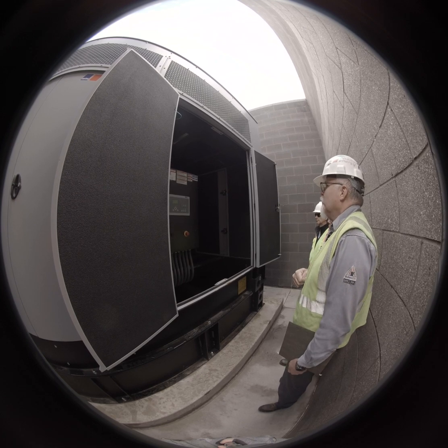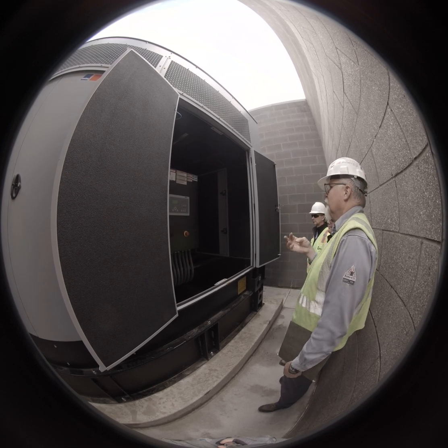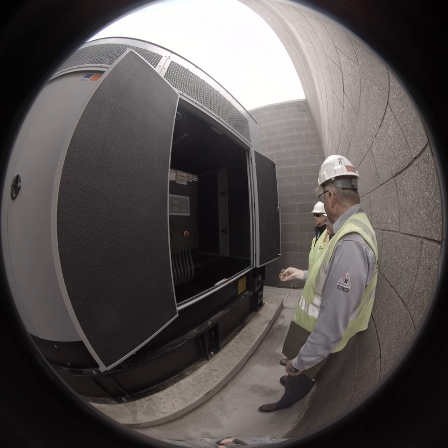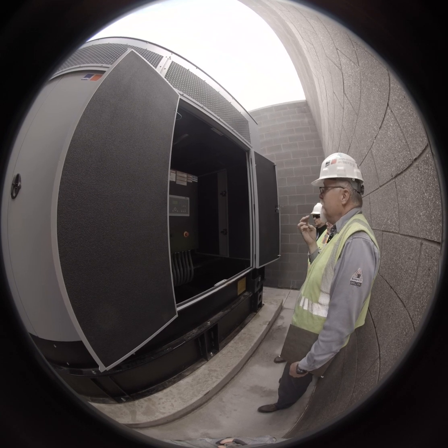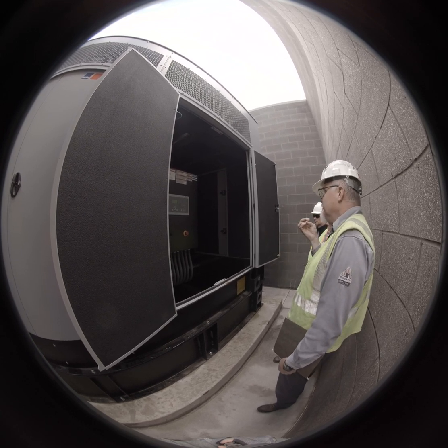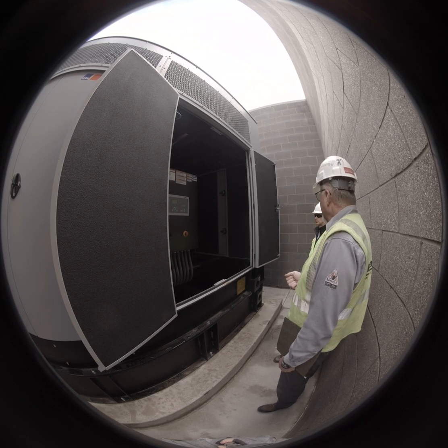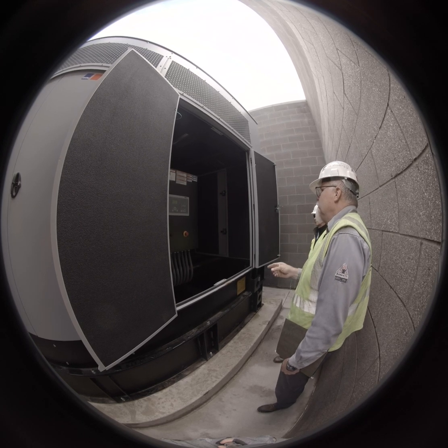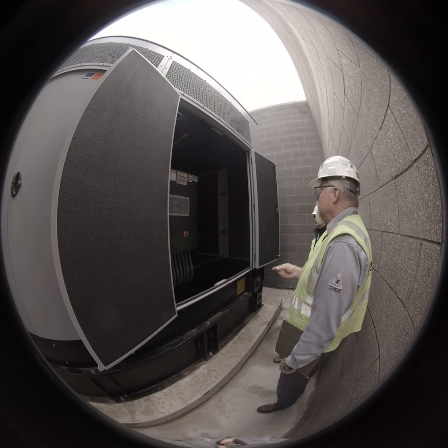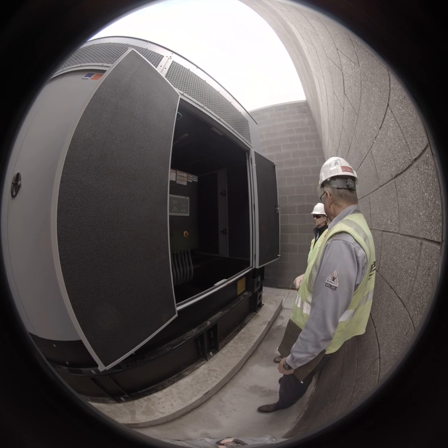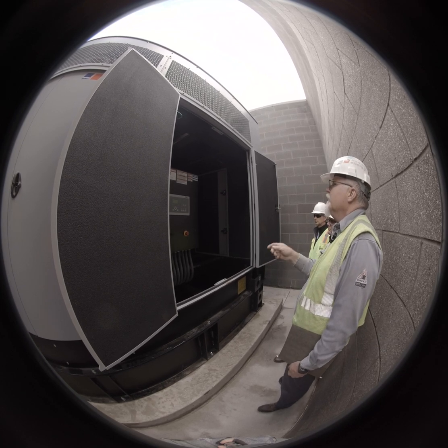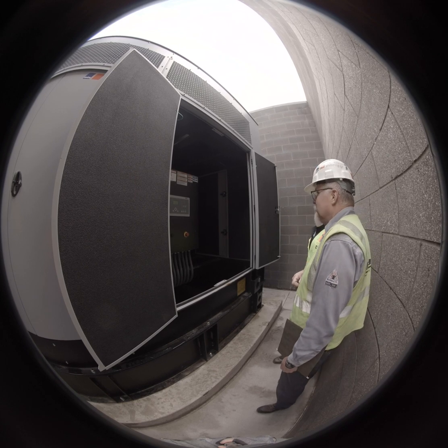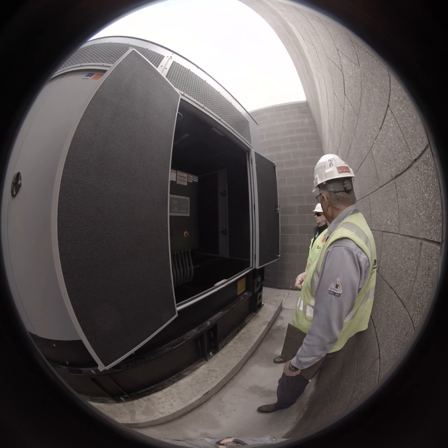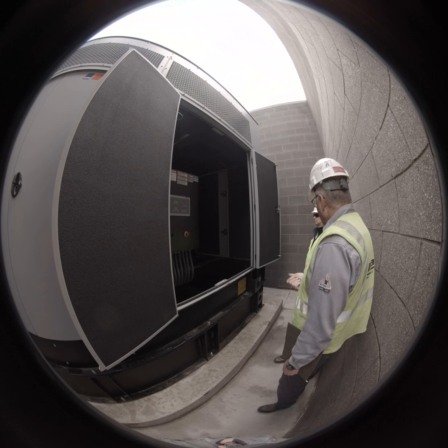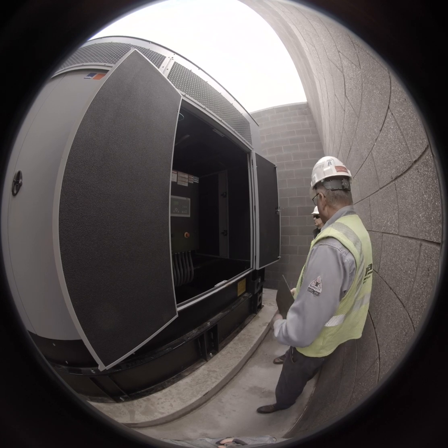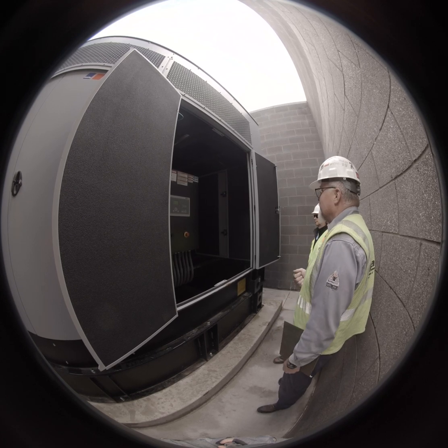Down in the bottom right-hand corner, we have three modes. We have the automatic, which is the way this should be left at all times. The off mode. Off mode is basically to turn the machine off. And if you have a shutdown alarm, you have to be in the off mode to reset it. Okay. Then you have the run mode. If you push the run mode, this machine will start up and it will run either until you shut it off or it runs out of fuel or some other factor shuts it down.